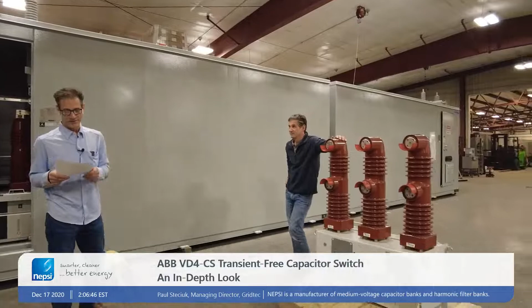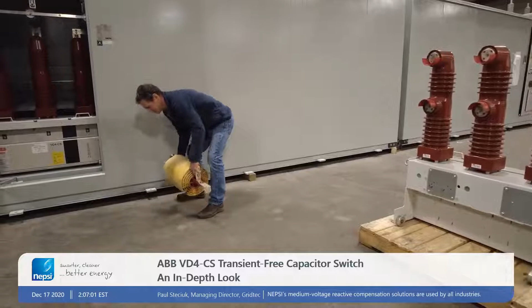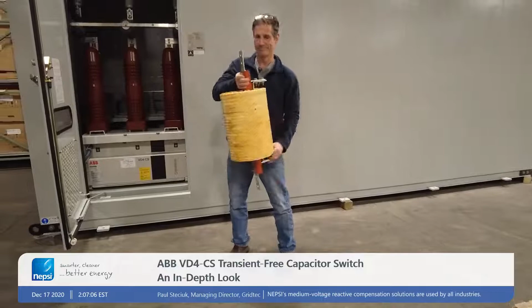So the VD4-CS is well suited for the renewables industry. It's got short lead times. They're stocked at NEPSI. That's key. It's a transient-free point-on-wave switching device. In other words, it's a zero voltage closing device. It's transient-free. There is no need for transient inrush reactors, and Pete will pick this up. During Tech Talk session 2, we talked about transient inrush reactors. When you use standard circuit breakers or standard switching devices, you need transient inrush reactors to limit the magnitude and the frequency of the inrush current associated with back-to-back switching. In capacitor banks like this, where we might have 10 megavars and 10 megavars, we would need these, and they can get quite big in the renewables industry because it's very common to have capacitor banks that routinely exceed 10 megavars in rating.